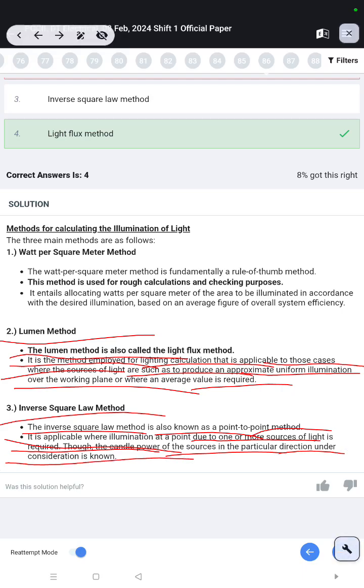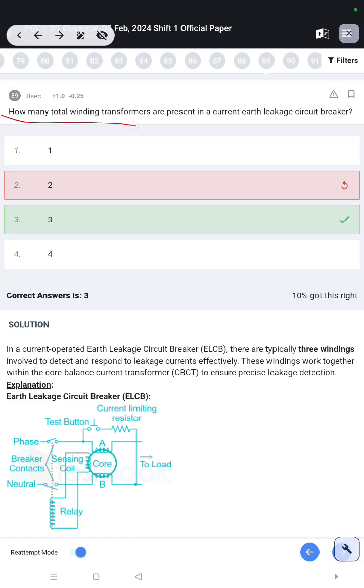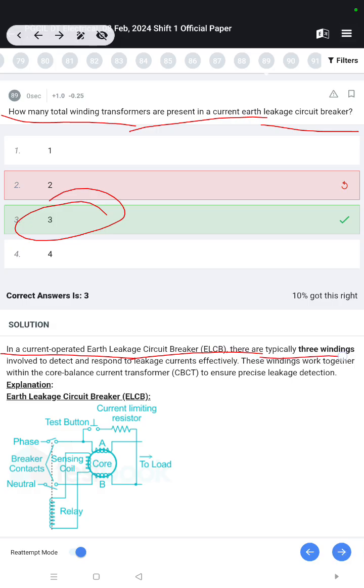How many total winding transformers are present in a current earth leakage circuit breaker? 3. In a current operated earth leakage circuit breaker (ELCB), there are typically three windings involved to detect and respond to leakage currents effectively. These windings work together within the core balance current transformer (CBCT) to ensure precise leakage detection. Earth leakage circuit breaker (ELCB).